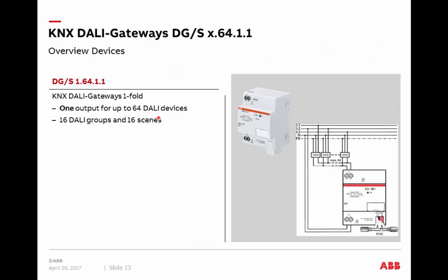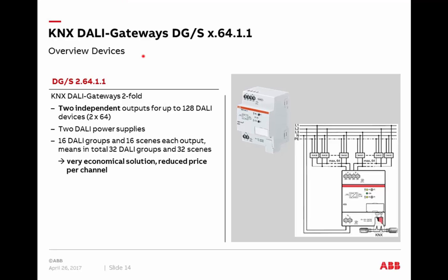Let's come to the components. Starting with the one-fold device, DGS 1-64-1-1 — one channel, one DALI output, up to 64 ballasts can be connected. You can create 16 DALI groups on the DALI side, 16 light scenes, and much more. The two-fold device, DGS 2-64-1-1, is a duplication of channel A to channel B — two independent DALI outputs for a total of up to 128 DALI devices, two times 64 ballasts per channel. Both have a 230-volt connection, and such a DALI gateway always serves as a DALI power supply for the DALI system.